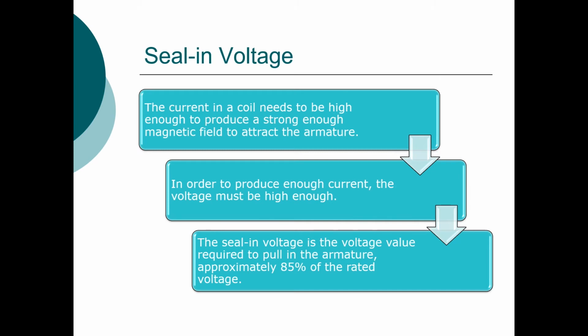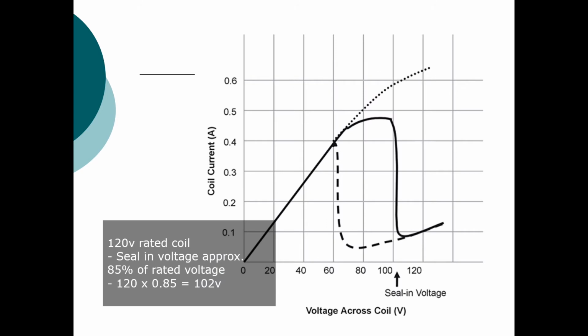If we were to graph the voltage levels of a variable transformer feeding voltage to a 120 volt coil, this is the type of graph that we would find. As we increase the voltage going to the coil, there will be a point in time where the armature will pull in and close the contacts. At that exact point, there is enough magnetic force applied to the armature to overcome the armature springs, and that is what we call seal-in. At that point, we should be at roughly around 85% of the total rated voltage of the coil.